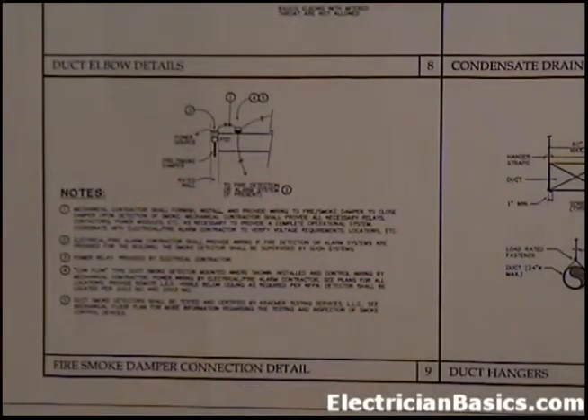Let's look here, Note 1. It says mechanical contractors shall furnish, install, and provide wiring to the fire smoke damper to close the damper upon detection of smoke. Mechanical contractors shall provide all necessary relays, contactors, power modules, etc., as necessary to provide a complete operational system. Coordinate with electrical fire alarm contractor to verify voltage requirements, locations, etc. Basically, this is saying who has to provide the equipment. What's nice about this is the architect becomes a judge and says, okay, you do this, you do this, you provide this material, you provide that. It keeps arguments down on the job, because I've seen people argue about who's supposed to do what, and it's not pretty.